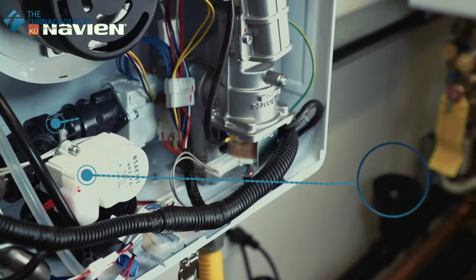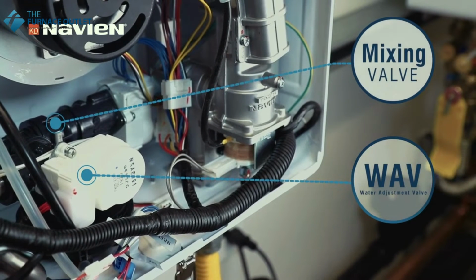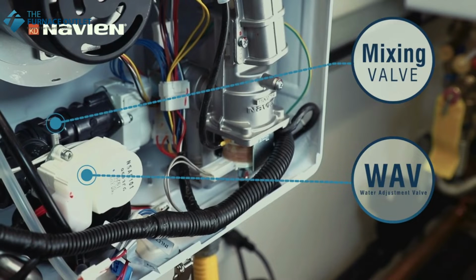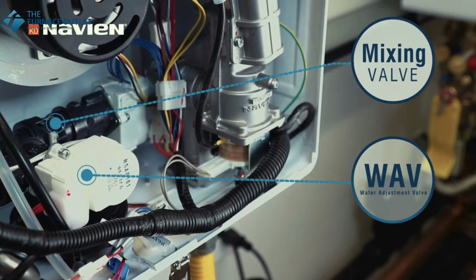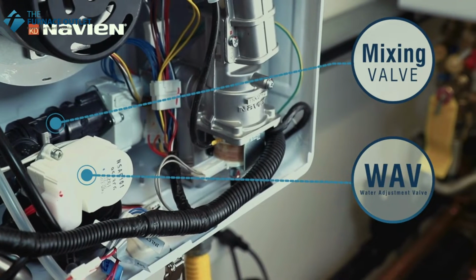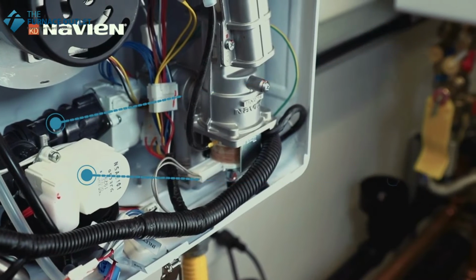So the NPN comes with a water adjustment valve and a mixing valve in every one of our units, all sizes, both the inside and outside unit. Those are both in there to ensure that we maintain a consistent outlet water temperature to deliver to the fixtures. The water adjustment valve controls the amount of flow going through the unit, and the mixing valve comes into play to help keep that water temperature constant coming out of the unit.